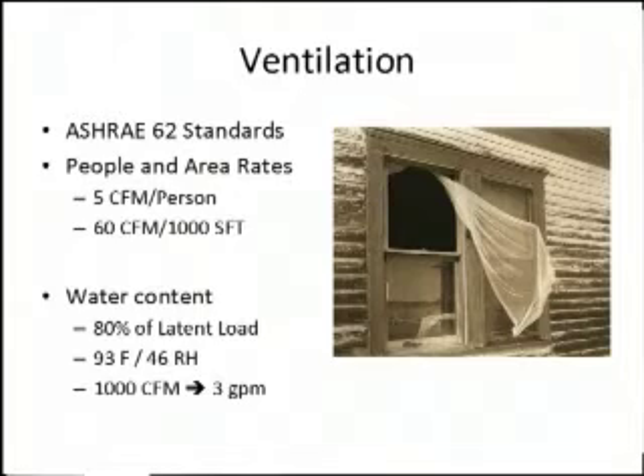These numbers here are our design conditions for Central Florida, and this is actually a very wet climate, as you know, you live here. You know there's a lot of moisture outside. So every 1,000 CFM we bring in generates about 3 gallons per minute of water that actually gets condensed into that condensate pan, if your units are working right. And that process is called dehumidification.